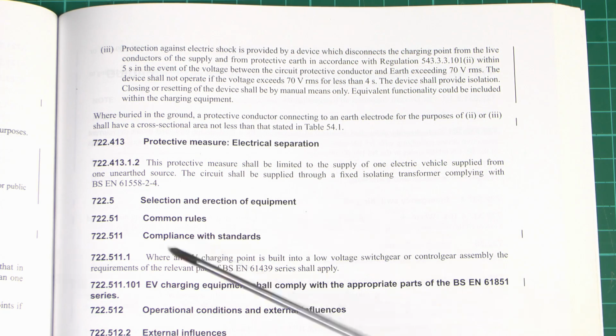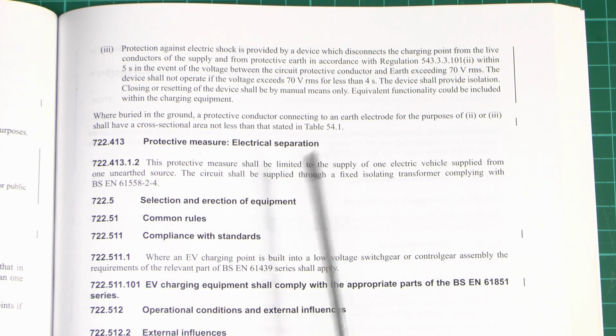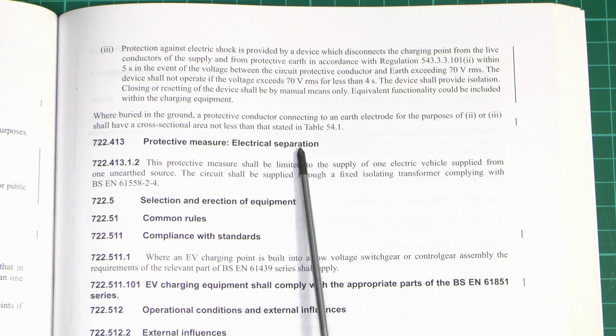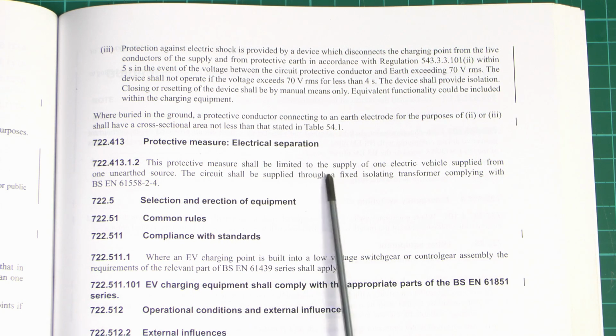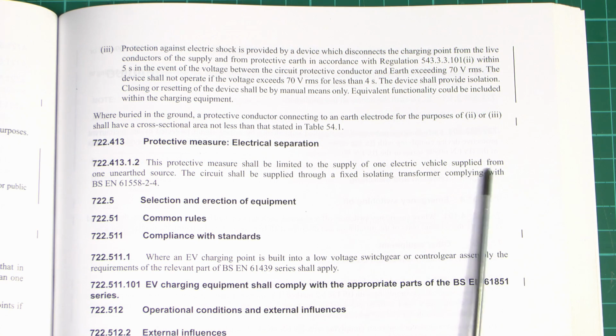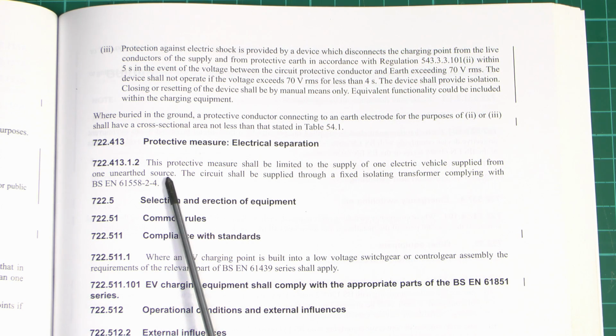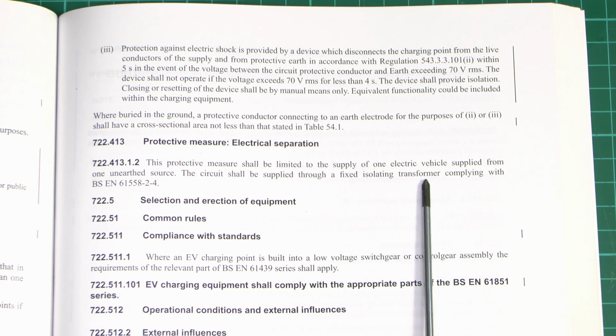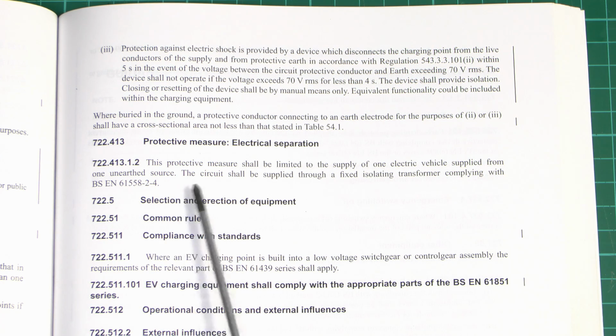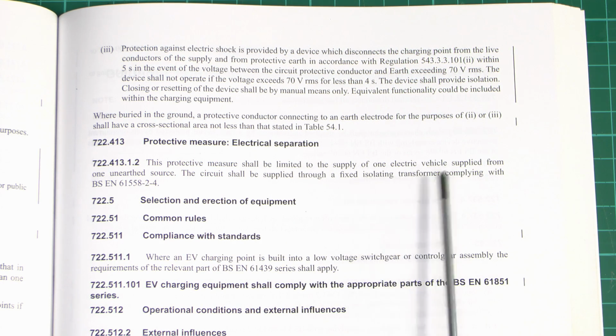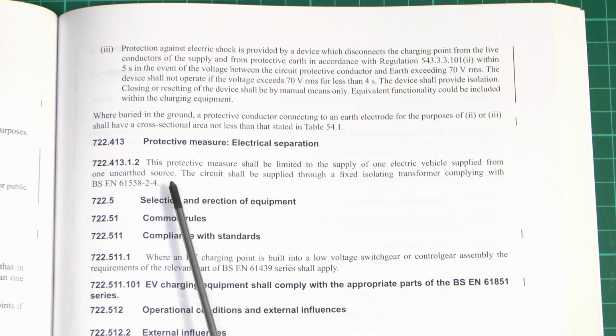Now let's have a quick look at some of the other things in section 722. You can use electrical separation if you really wanted to, but as it says here, this is limited to the supply of one electric vehicle supplied from one unearthed source, and it's supplied through a fixed isolating transformer complying with this standard. So you could use an isolating transformer, but providing it's only providing one electric vehicle charging point.